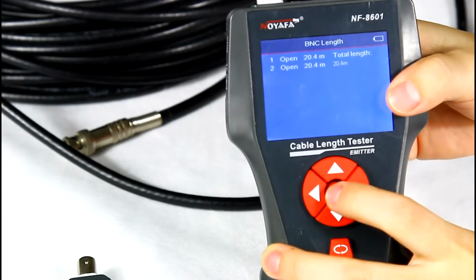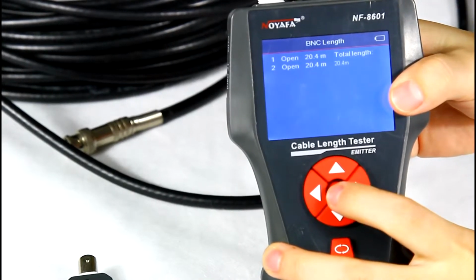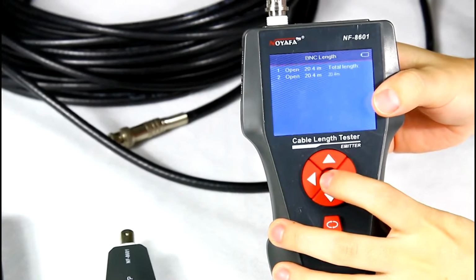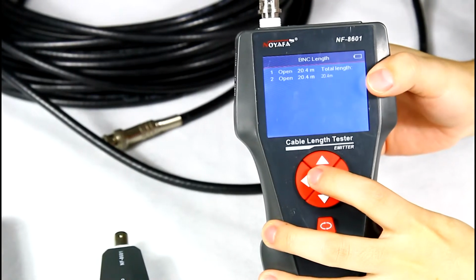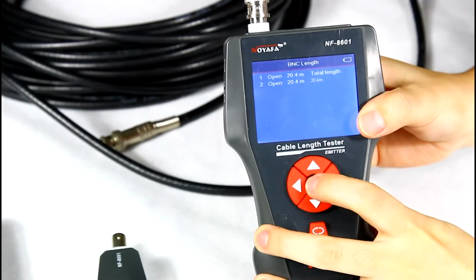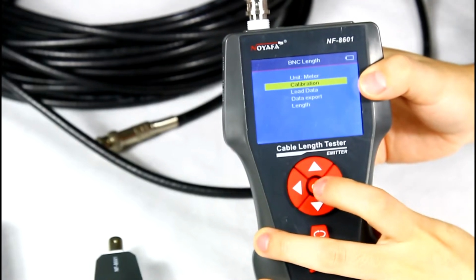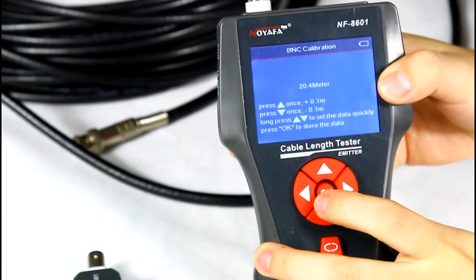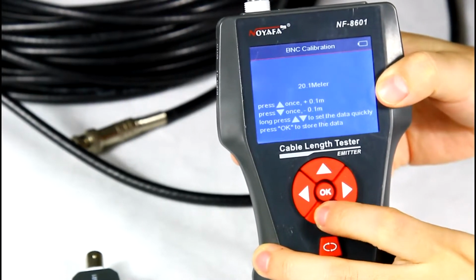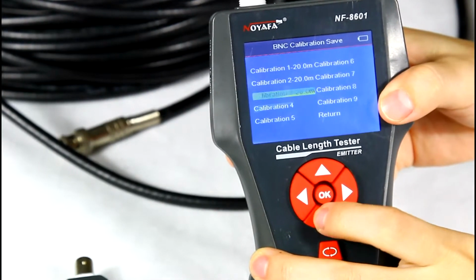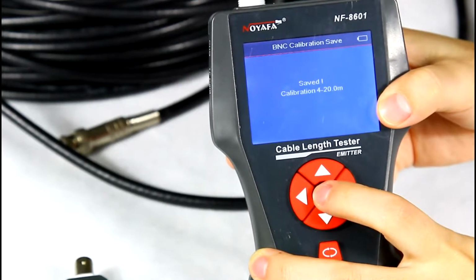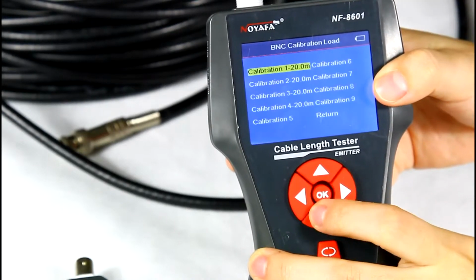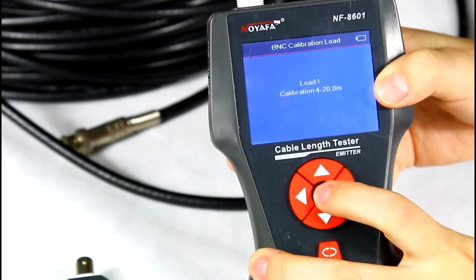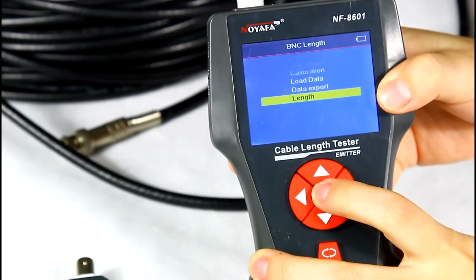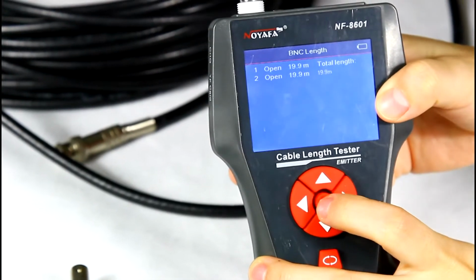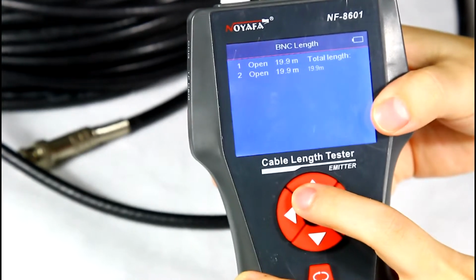The accuracy for this device can be up to 99%, but if the error is a little large, we can use the calibration function first, then measure the cable length again. Here, let me show you how to calibrate. We go back and choose the calibration function. Here we adjust the length to 20 meters. We save the data to calibration 4. And we need to load the data. And we go back and test the length again. The result shows us the cable is 19.9 meters. The result is more accurate.